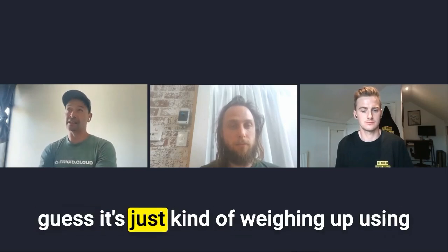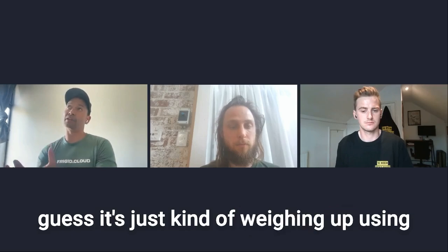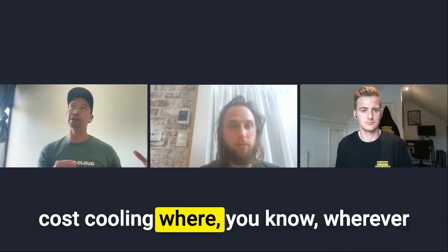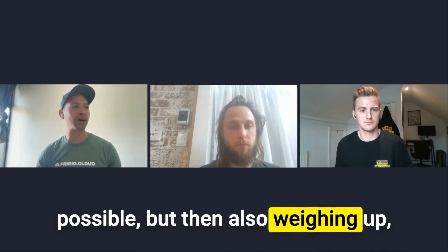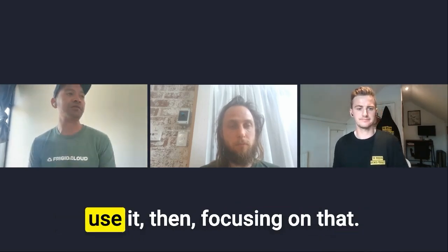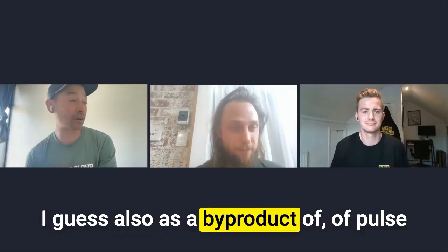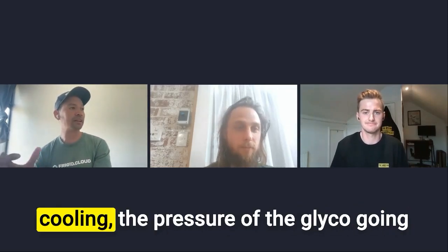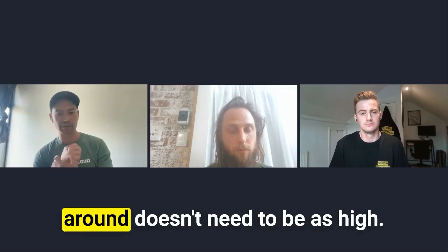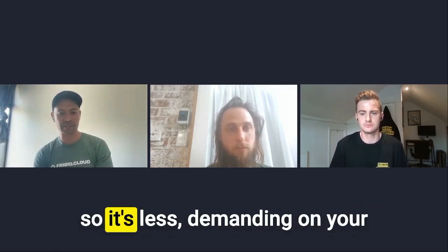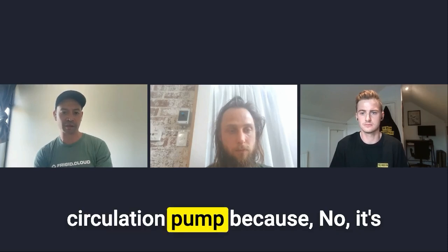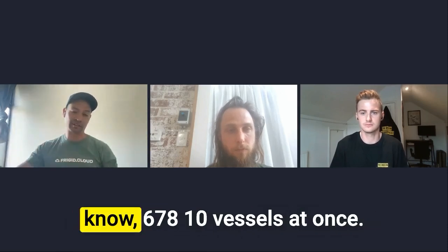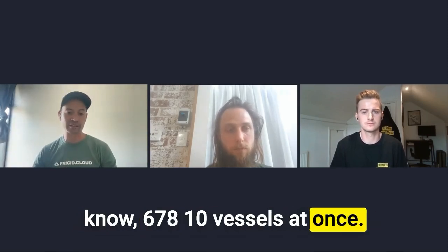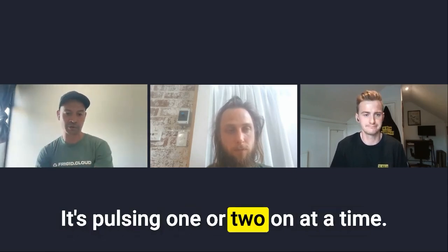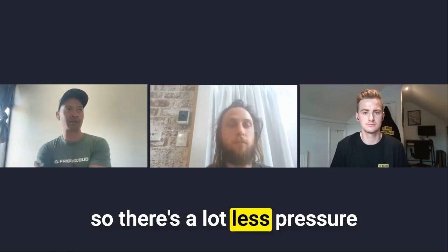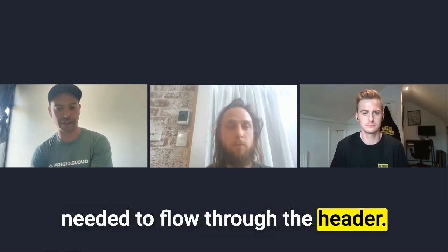Yeah, it's just weighing up: using pulse cooling wherever possible, but also weighing up if there's a need to not use it, then focusing on that. I guess also the byproduct of pulse cooling is that the pressure of the glycol going around doesn't need to be as high, so it's less demanding on your circulation pump. It's not trying to pump into 6, 7, 8, 10 vessels at once. It's pulsing 1 or 2 on at a time, so there's a lot less pressure needed to flow through the header.